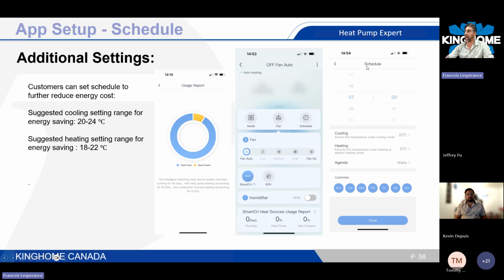And you can also add a schedule via the app. If the customer wants the system to start at a certain time and end at a certain time, it's much easier to use the app to create a schedule instead of clicking buttons on the thermostat. You can just sit on your couch and do everything via the app. It's really straightforward. You just select your temperature, period of the day, and hours. You can set up multiple schedules, and you choose which days you want each schedule to be active. In blue, it's active. In gray, it's disabled.